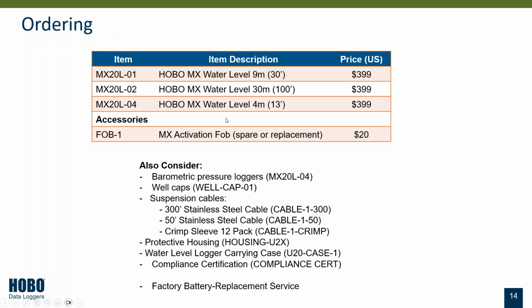In terms of details, we're selling these in 3 different ranges: the 30-foot range, 100-foot range, and 13-foot range, all at the same price. If you go for a narrower range, you get better accuracy within that range. But you need a range that accommodates your full range of measurements and the depth you'll be deploying the logger at, so you may need to go for one of these wider depth ranges.